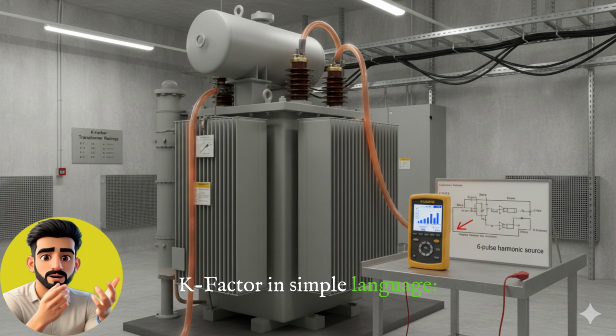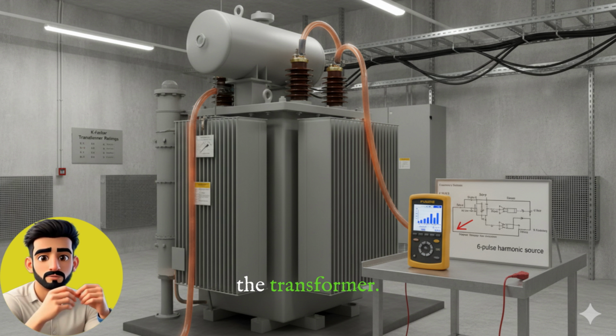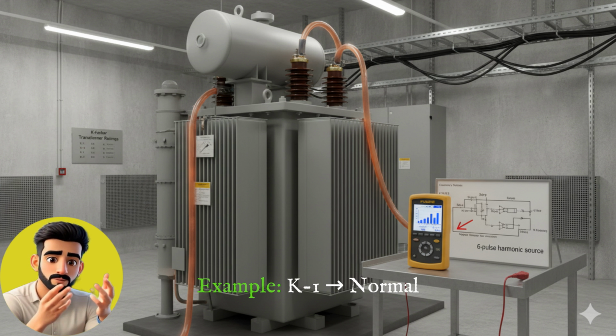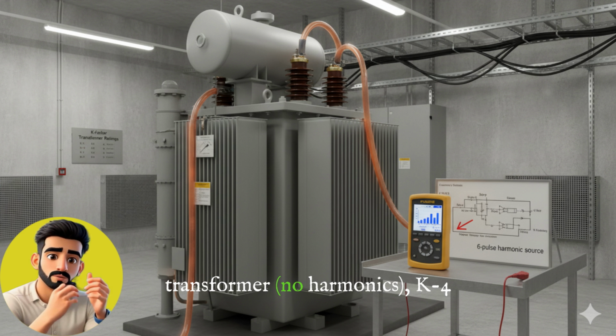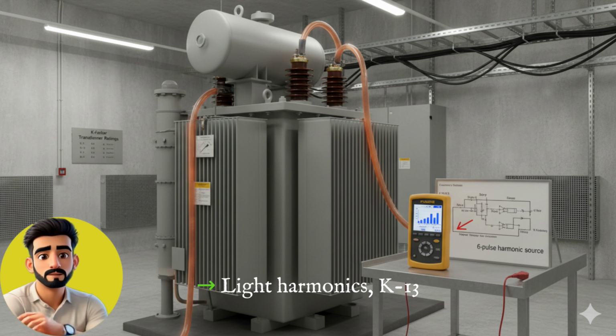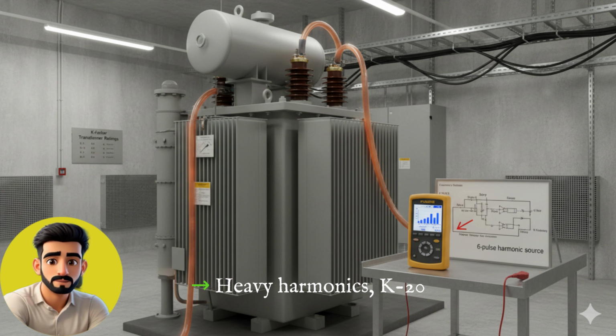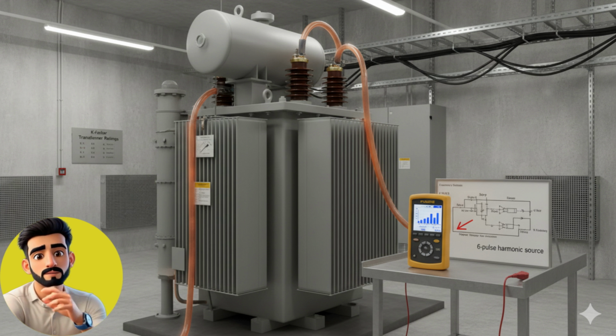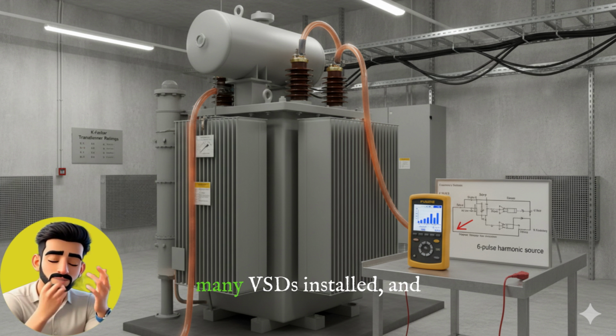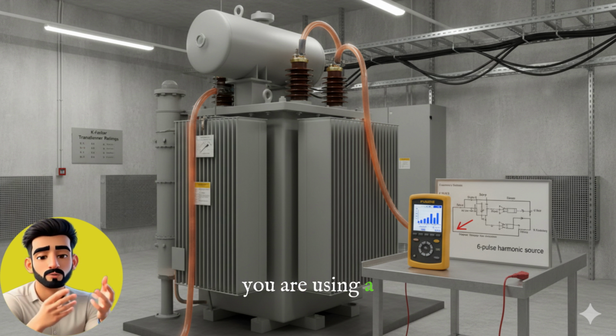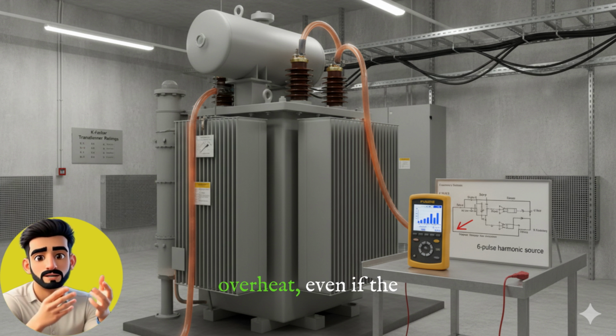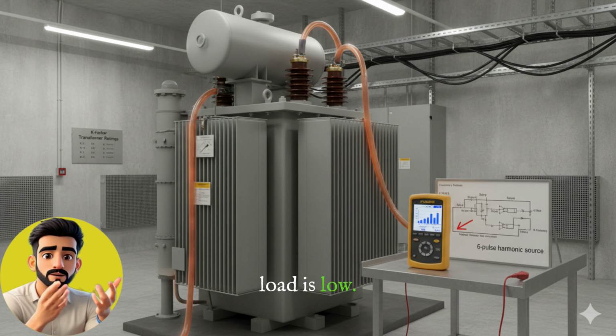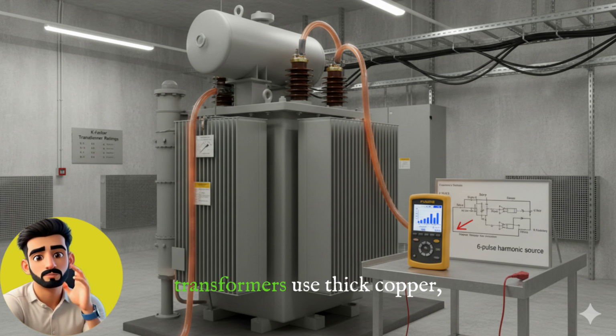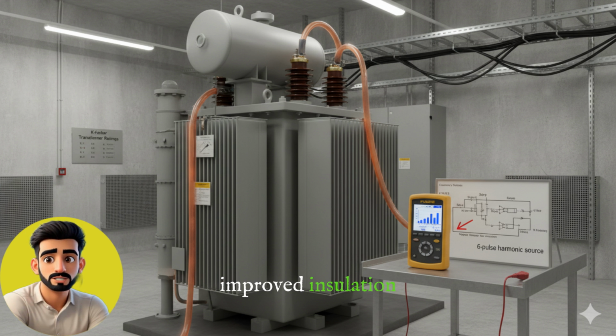K factor, in simple language, is the harmonic tolerance of the transformer. Example: K1, normal transformer, no harmonics. K4, light harmonics. K13, heavy harmonics. K20, extreme harmonic environment. If your plant has many VSDs installed and you're using a normal transformer, it will overheat even if the load is low. In such cases, K-rated transformers use thick copper, improved insulation, and a low-loss design.